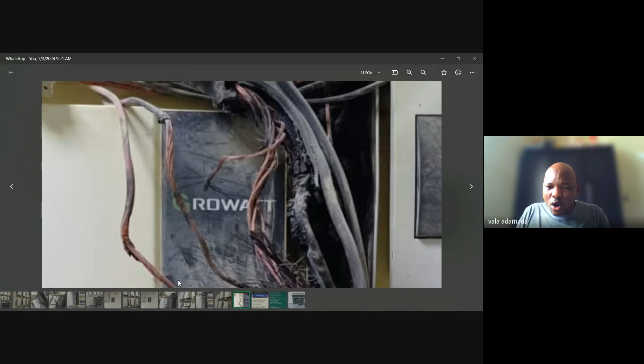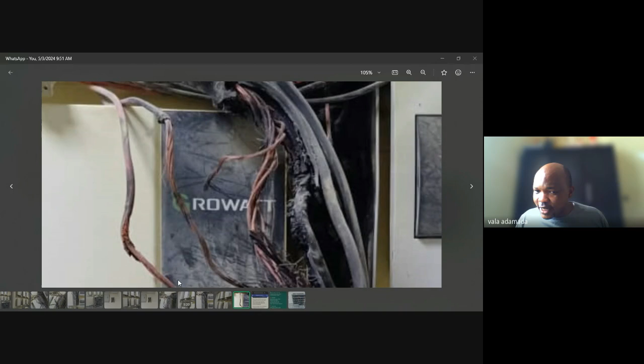Especially when that cable is working close to its threshold or maximum, everything along the line has to work optimally. So cable lugs must also be identical. I have no problem saying that, someone else may tell you it's bad, but if you cannot get identical ones, you have to make do while taking these precautions.